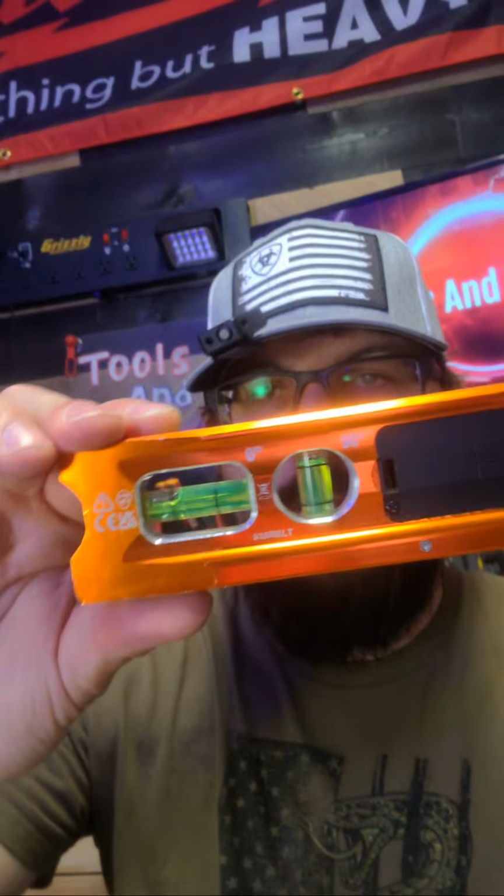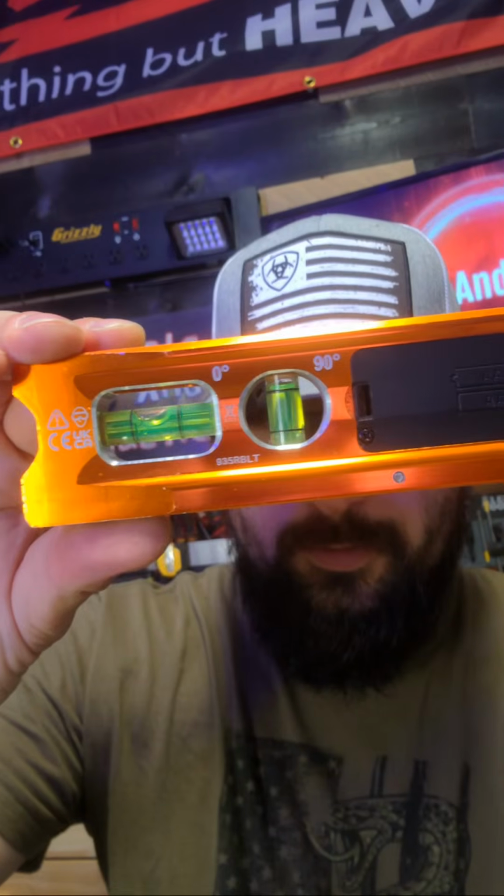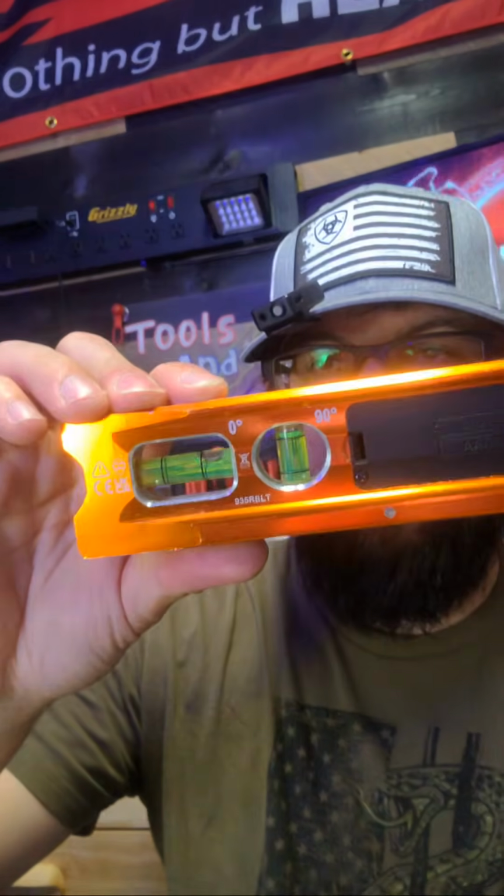And then if you get this on your level bubble, you just make sure that your 90 also has that bubble. So you're purposely bending a crooked 90 just to match that bubble. Because if this bubble matches the other bubble, you've got a 90-degree bend. You just line up your bubbles. So if you're on a scissor lift and it's not level, you just line up to whatever your bubble showed.